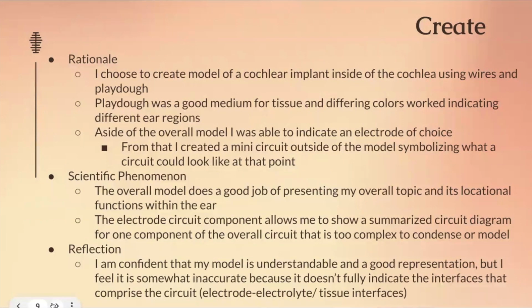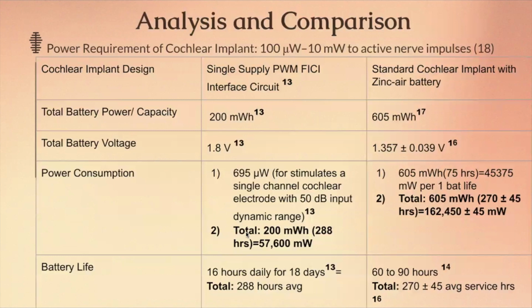And then for my analysis and comparison, I compared a fully implantable cochlear implant circuit with a zinc-air battery, which is standard in cochlear implants. I compared their total battery power or capacity, and as seen, the zinc-air has a higher capacity compared with the fully implantable. The total voltage, though, was greater for the fully implantable cochlear implant, 1.8 compared to approximately 1.4 volts. And then I analyzed their power consumption.